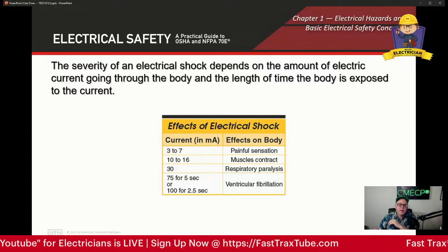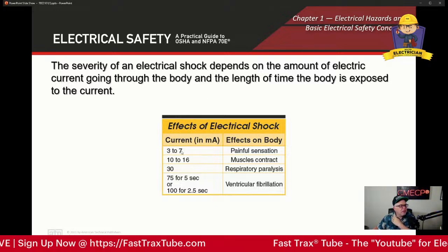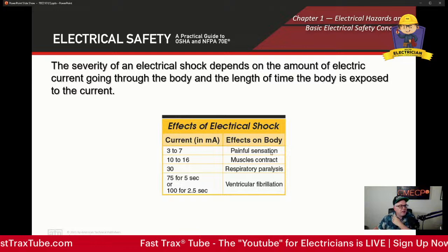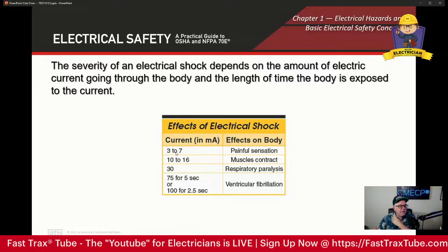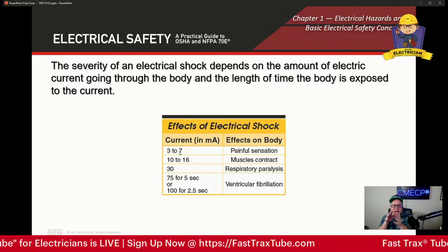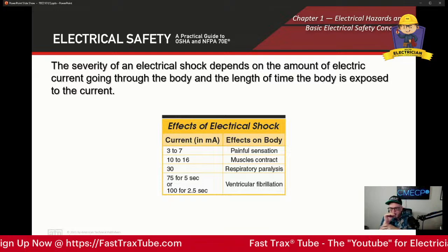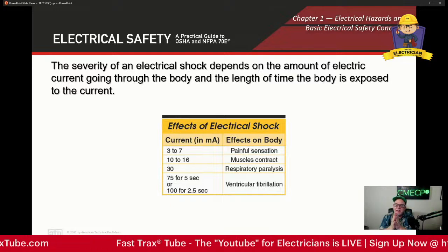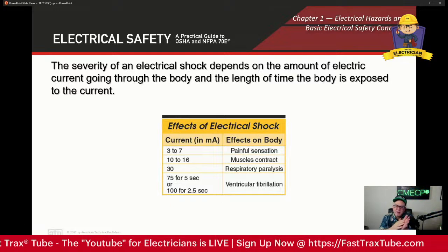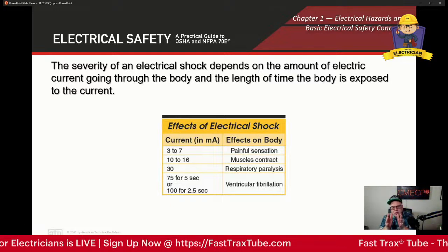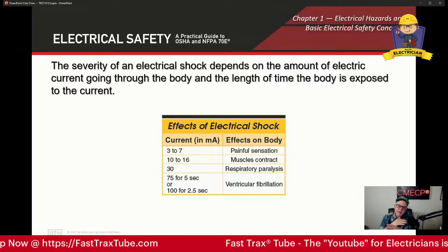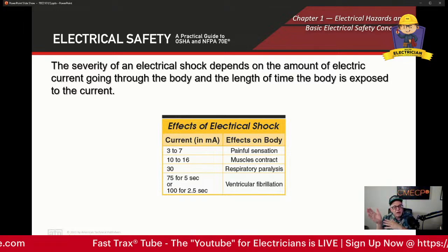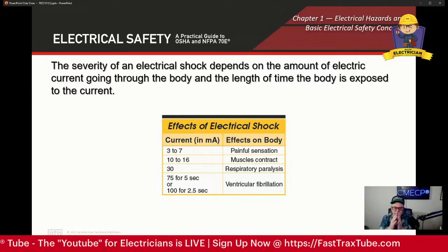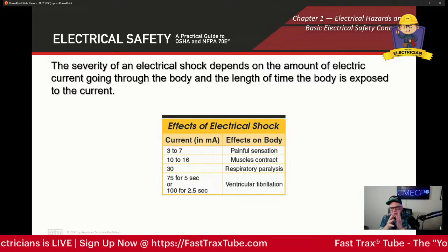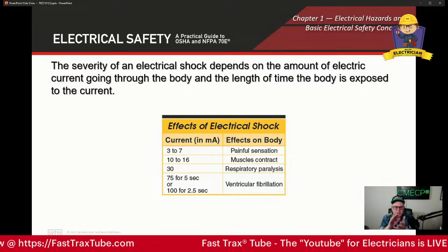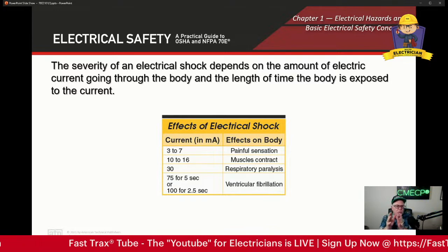So if you look at the stats here, 3 to 7 milliamps is a painful sensation. Remember that 5 milliamp is where the GFCIs, Class A GFCIs, are sitting. A GFCI Class A is designed so that at 4 and less, they're not supposed to activate, and at 6 and greater, they're supposed to make sure they activate. We call it 5 nominal. So that bridge is right there at 5, giving manufacturers a little bit of left and right they can move, but that's what we all base it on.